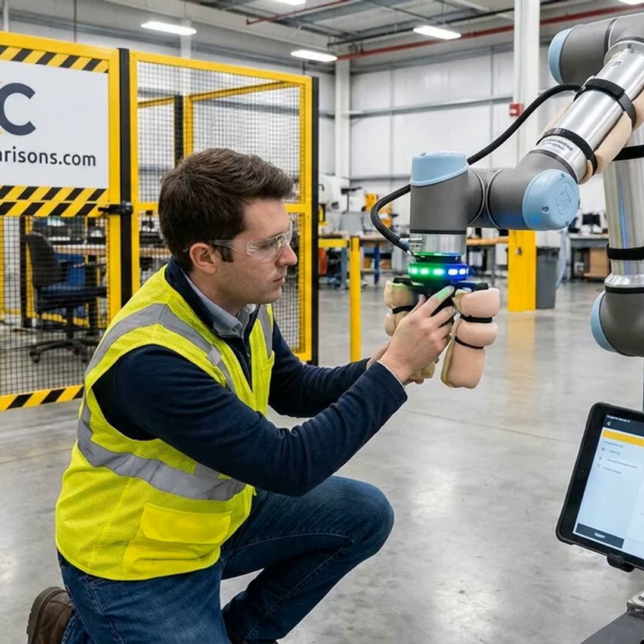Measurements. Record the time when the person enters the detection field, the time when the camera first reports the person, the time when the safety controller changes robot speed, the time when the stop signal is issued, the time when robot speed begins to fall, the time when the robot reaches a safe stop, minimum measured human-robot distance, false stop rate, missed detection rate, and behavior after sensor failure. Use synchronized timestamps from the 3D camera, the safety PLC, the robot controller, joint encoders, an independent high-speed camera, and a separate position tracking system. The key result is not the average reaction time. It is the worst-case reaction time, including network delay, filtering, decision time, drive response, and mechanical stopping.